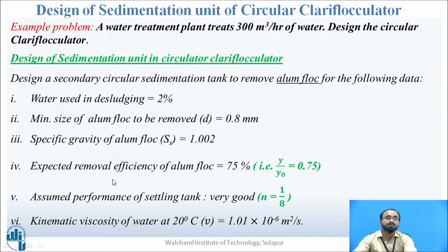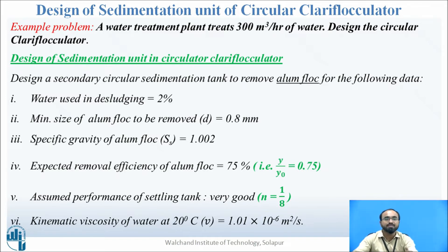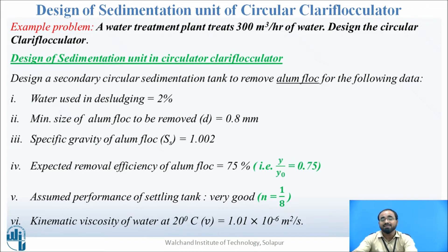Expected removal efficiency of alum flock is 75 percent, i.e., Y by Y-naught equals 0.75. Assumed performance of the settling tank is very good, so N is taken as 1 by 8 (for good condition it would be 1 by 4). Kinematic viscosity of water at 20 degrees Celsius is taken as nu = 1.01 × 10⁻⁶ m²/s.